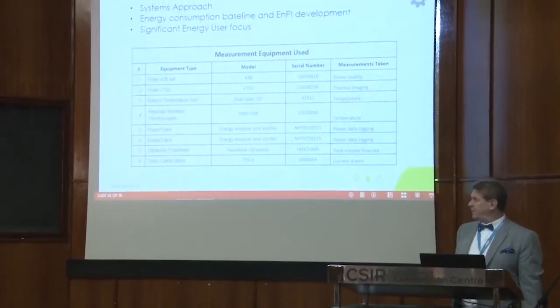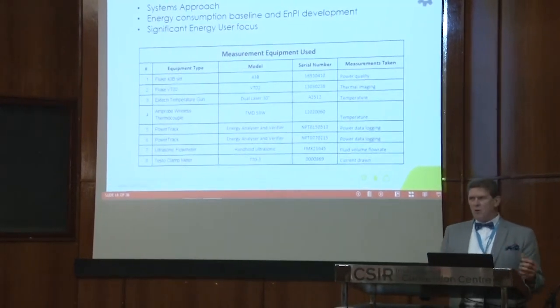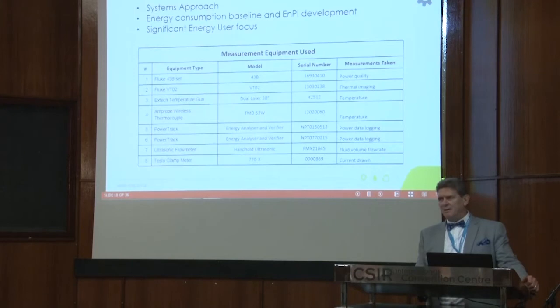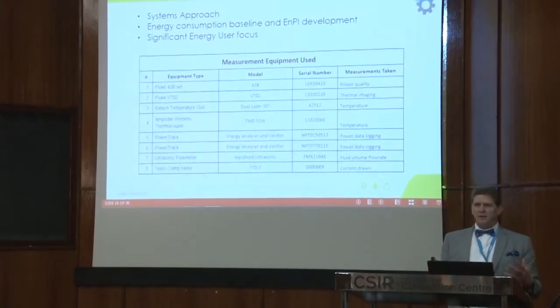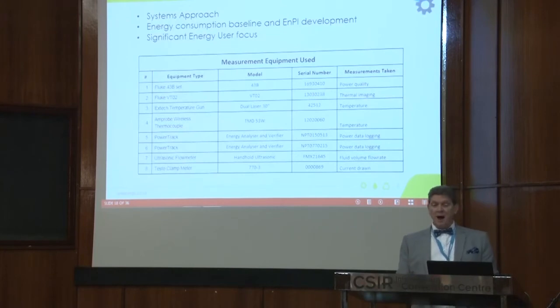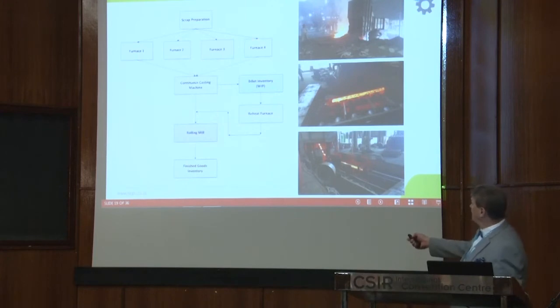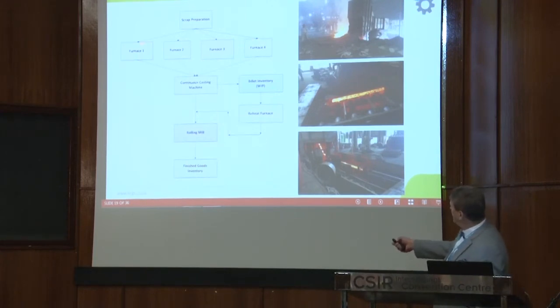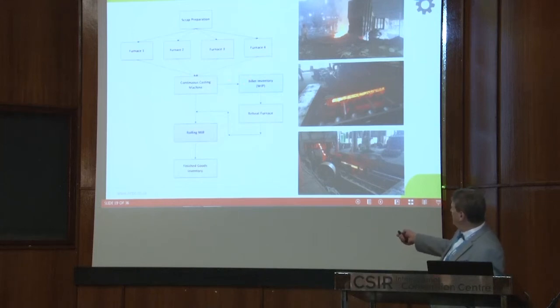We took along a range of equipment — predominantly power quality analysers, power data loggers, and thermal imaging cameras — because we needed to capture how they were using power. The process essentially saw a lot of scrap being fed via magnetic hoist into induction furnaces, then into a continuous casting machine, a rolling mill, and ultimately finished rebar. There was also a side process where from the billet inventory we had a reheat furnace with that same process.